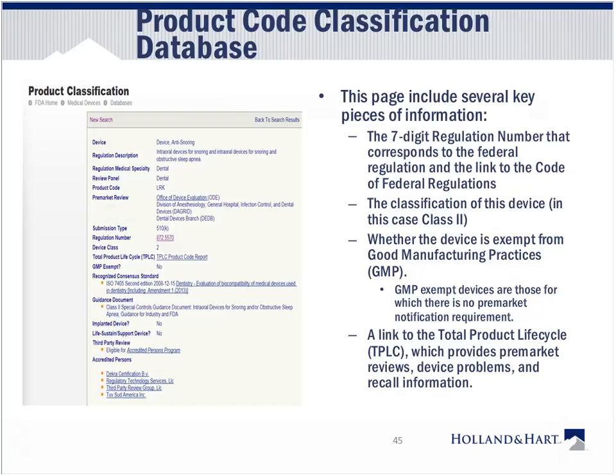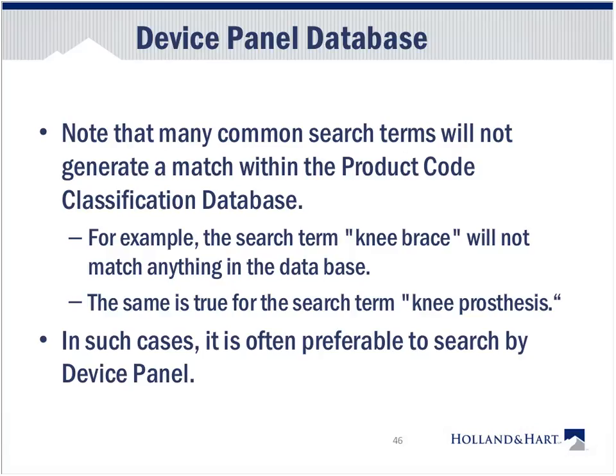So the important parts are the 7-digit regulation number, that's the 8725570, the classification of the device, which is 2, whether the device is exempt from GMP, good manufacturing practices, that is whether or not it has to go through the 510K process, and then a link to the total product life cycle report, which provides pre-market review, device problems, and recall information. Can be very, very helpful when you're looking at a new device.